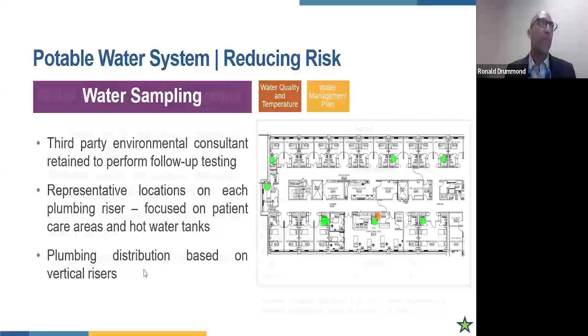Although it's not as effective as hyperchlorination, it's well documented that high temperature is a good measure to help control or eliminate Legionella. And actually, I should step back from saying eliminate Legionella. Just wouldn't like that. So we can control it with a high temperature purge. One of the difficulties with this in healthcare is that the hot water temperature needs to be raised throughout the network, not just at the tanks.